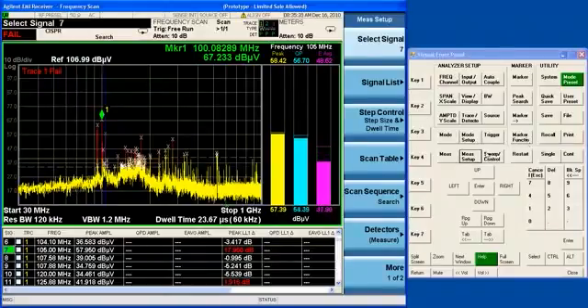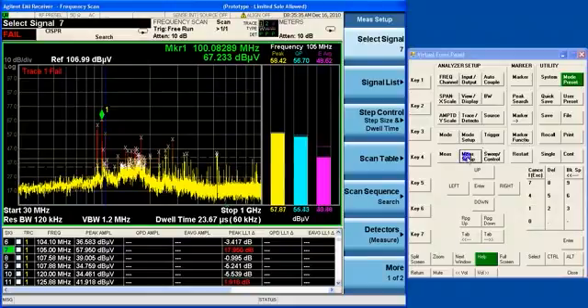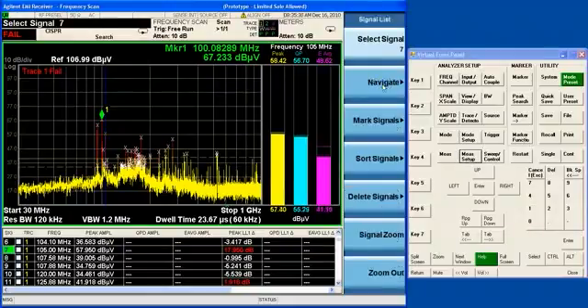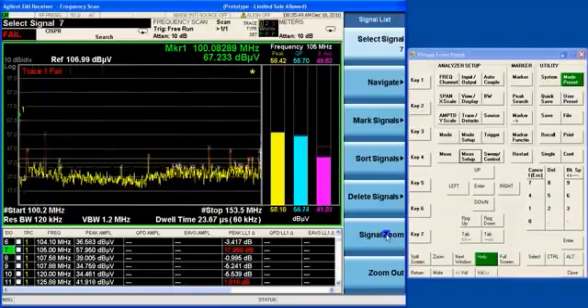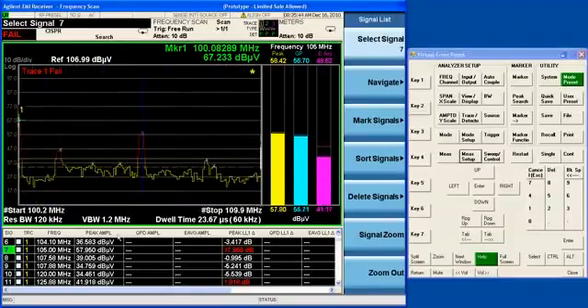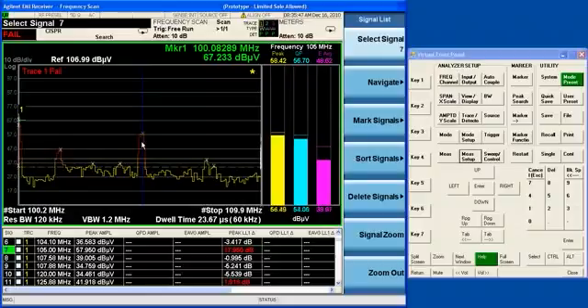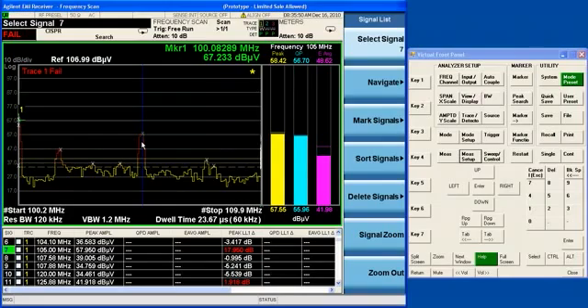Now when you're in the signal list, remember we had the marker zoom function. With the signal list, you also have the signal zoom function. So I can zoom in on this, my selected signal, and I can see, yes, I'm not really centered on that signal. Now I'm going to adjust the frequency of the meters and try to get them better centered up on this signal.